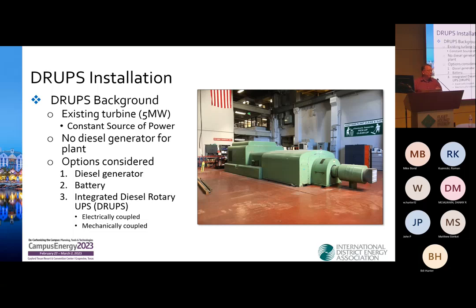6 megawatts to the hospital, 4 megawatts to the campus. So we thought, okay, we got to get one for ourselves. But that still left that 10-second startup gap. In 10 seconds, the whole plant shuts down and it takes us 4 or 5 hours to recover. Again, the hospital can't live with that.